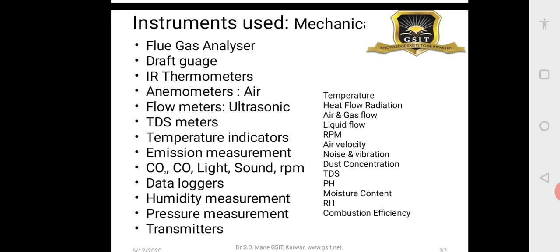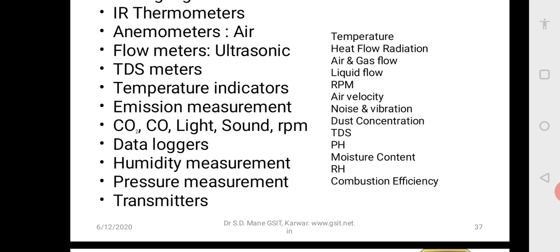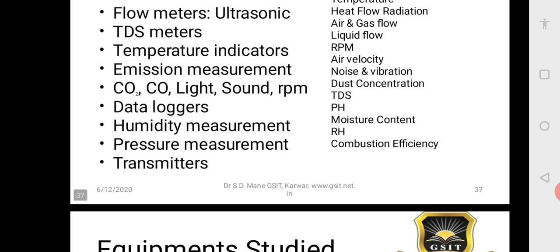Now let us look at the instruments used for energy audits, like mechanical ones. What are the parameters you measure? You measure temperature, heat flow, radiation, air flow, liquid flow, RPM, air velocity, noise, vibration, dust, TDS, pH values, moisture, relative humidity, combustion. For measuring these parameters, you have flue gas analyzers, draft gauges, IR thermometers, anemometers, flow meters, TDS meters, temperature indicators, emission measurement. And nowadays you have multitasking equipment which measures 3-4 quantities in a single instrument, with data logging facilities, pressure measurement, humidity measurement.